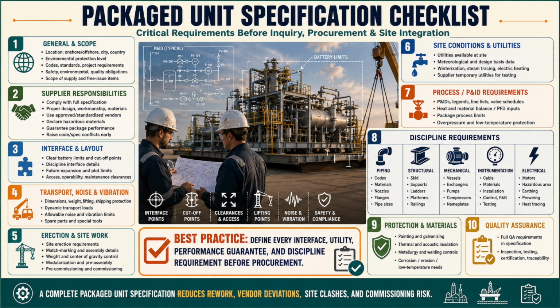Decide whether each utility will enter the package through a single common connection or multiple service-specific connections. Specify mating flanges, blind flanges, flange ratings, facing, materials, gaskets, and bolting. Identify prohibited or non-standard pipe sizes. Small deviations in pipe size philosophy can create unnecessary field reducers, special components, and stocking problems. Nozzle load limits must be stated.